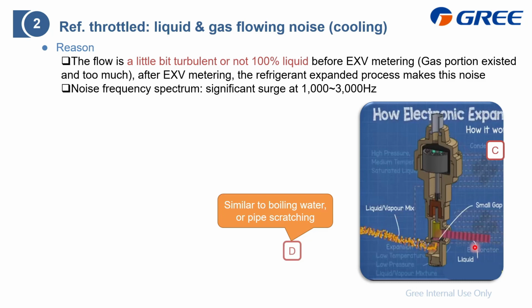We need to ensure that the refrigerant entering this part is completely liquid. What is the benefit we can get from making it 100% liquid? When we do the metering, it makes the process peaceful, and the noise will also be very low. In the opposite case, what is the consequence? If we cannot ensure it is 100% liquid, the process will be turbulent, and the noise will be very loud or significant.